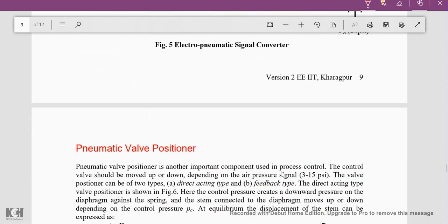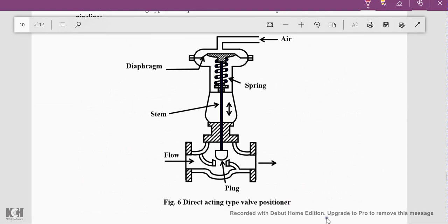Now the last part of pneumatic control components is valve positioners, which are very popularly used in many process controls to control the output at a particular value. Valve positioners are of two types: direct acting type and feedback type. In the direct acting type shown here, the control pressure acts on a diaphragm connected to a spring.